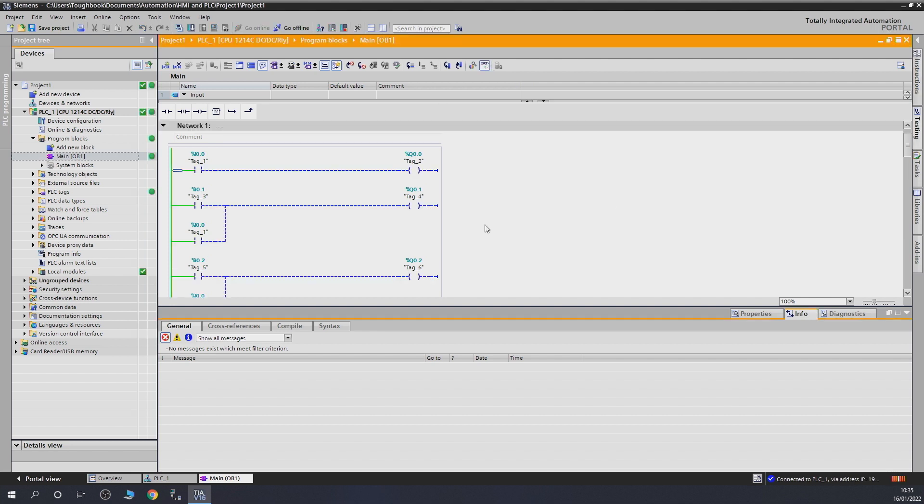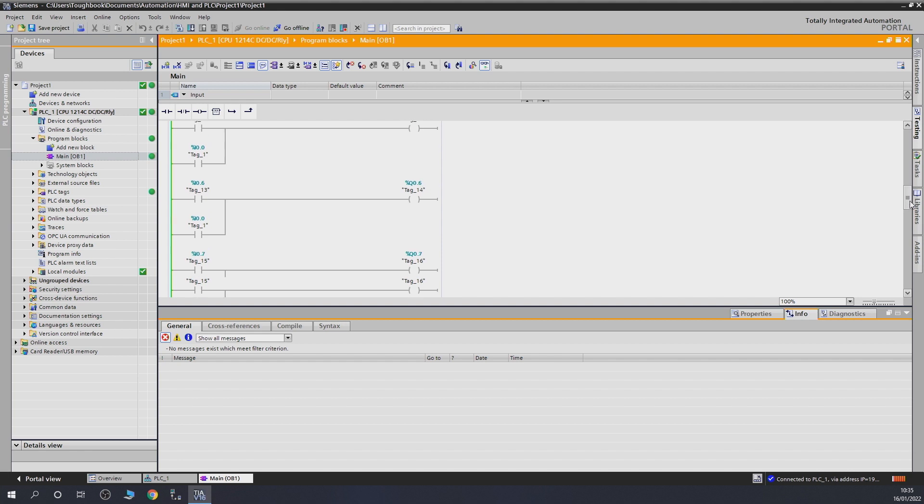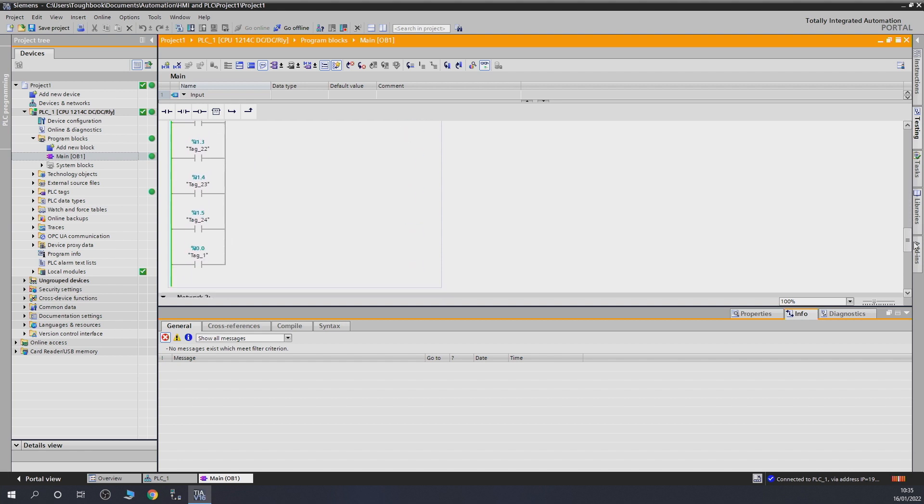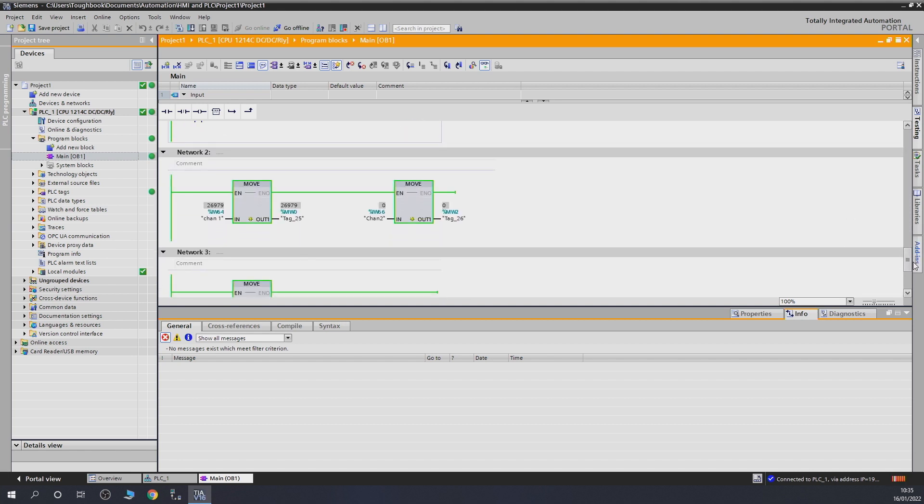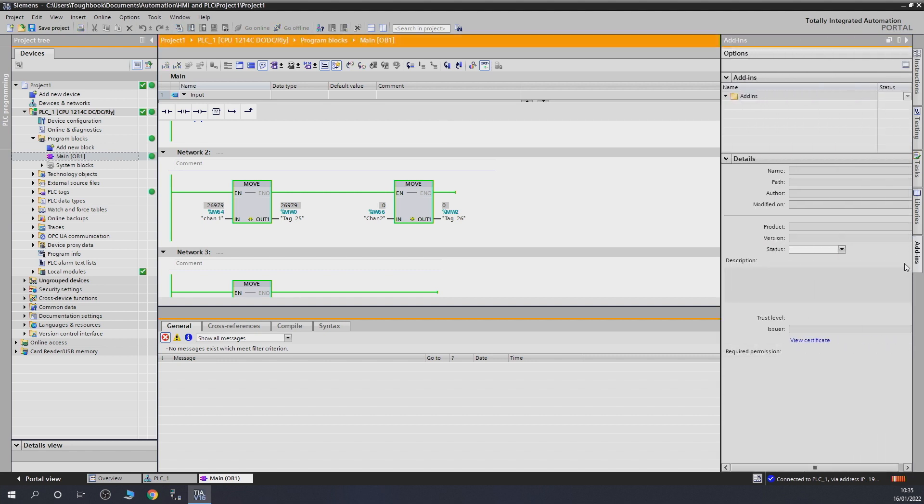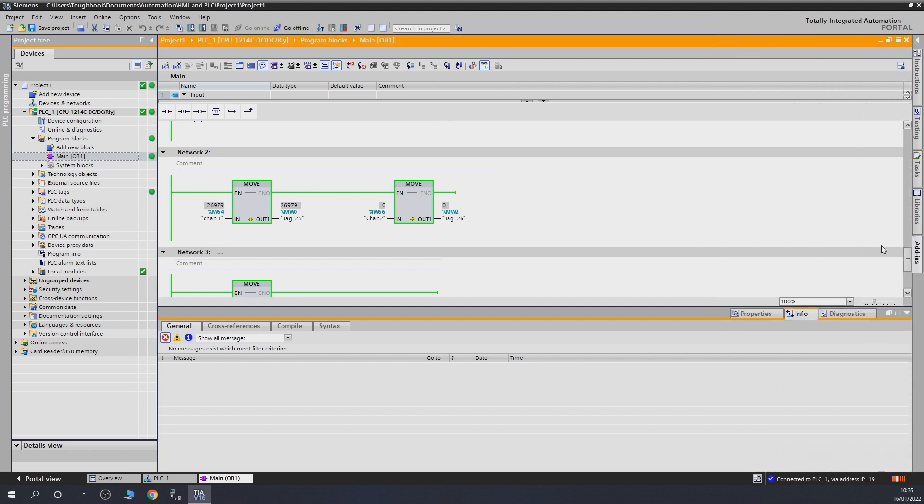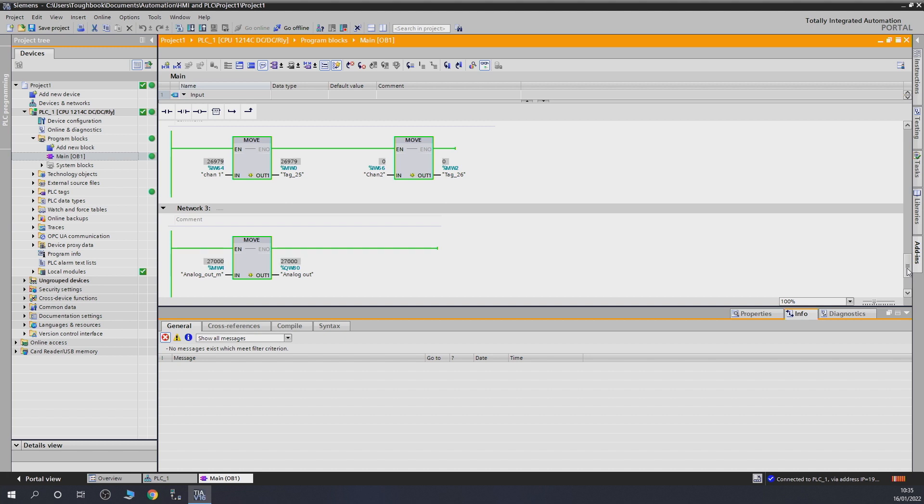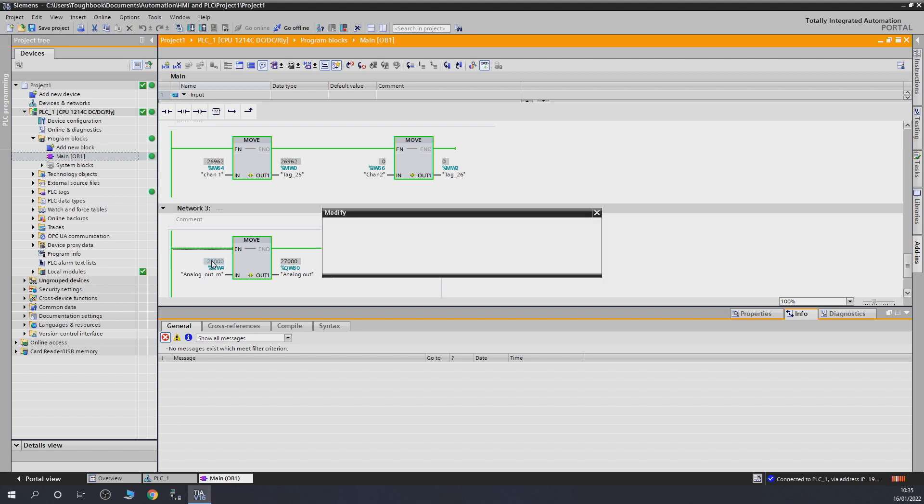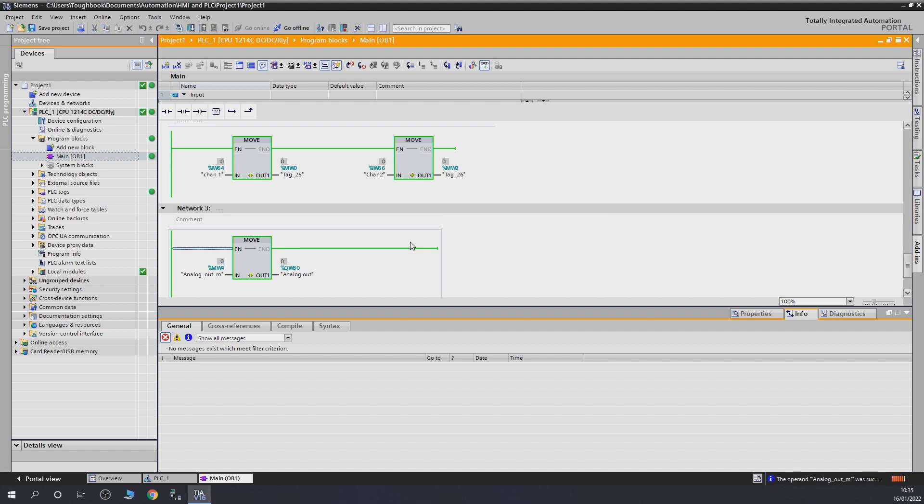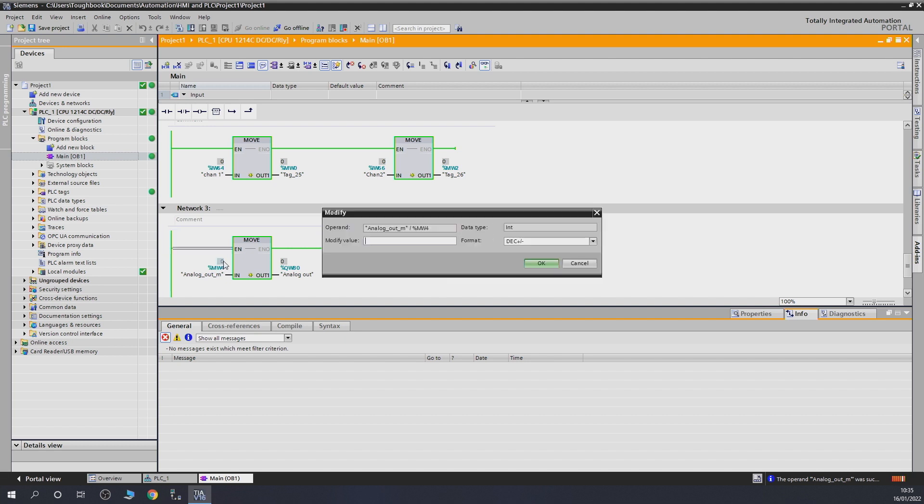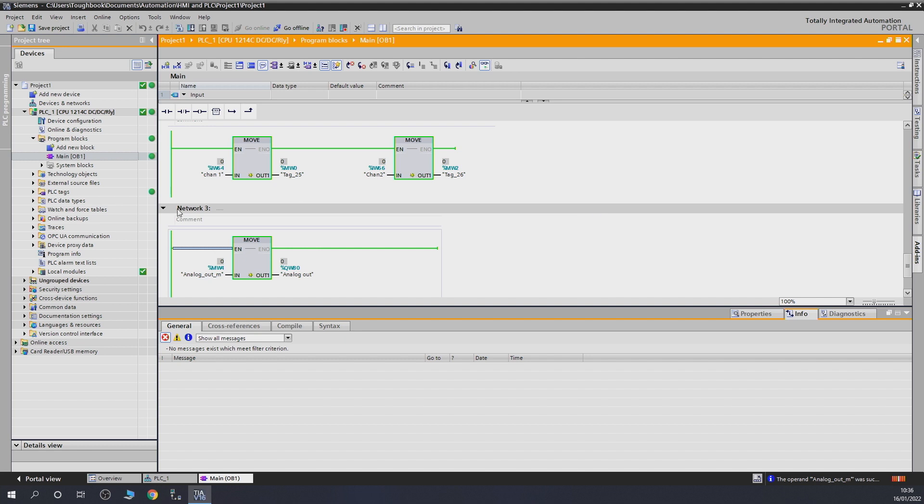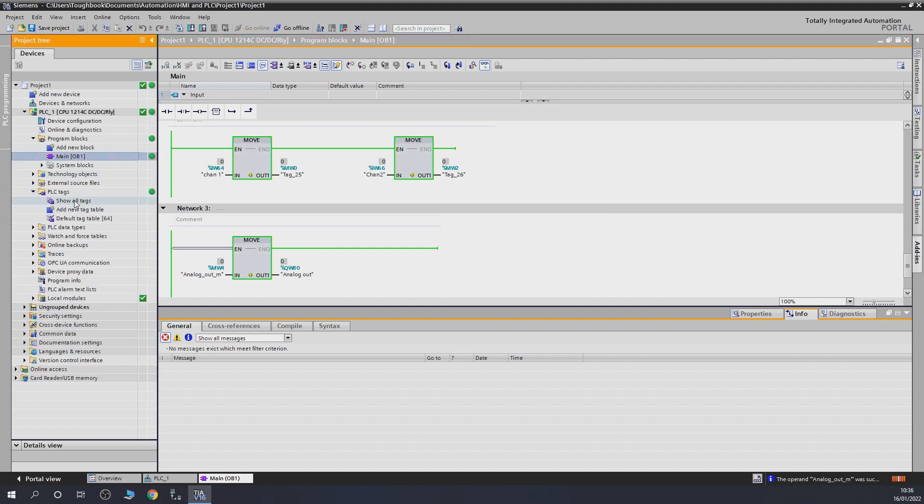So what we're going to do, we're going to go into the watch table and go in here, let's check out how the analogs are coming. So it looks like, did I have digit in there? Oh, that's because I'm using this particular part of the program I'm using for the other controllers. Looks like it saved that 27,000. Or no, I'm not sure now. So yeah, so here's 27,000 coming out. So normally it would be zero. Let's do that. So look at that, that's working really well. So basically what you're doing is sending an analog signal from here, which is in integer value. If you go into your PLC tags and show all tags, as you can see, integers.